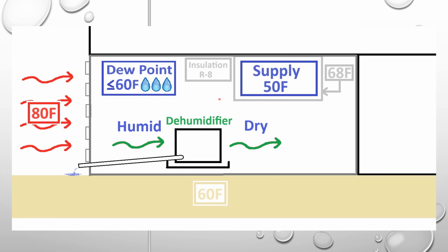If you have a duct system that's in unconditioned spaces, attics, crawl spaces, carports, we can't do anything about the outside temperature. The only time I get the chance to control that temperature or to stop the humidity from going in there is if you put an encapsulation around that, an encapsulated attic or just sealed up boxing. Otherwise, it's equivalent to putting a water pump in a lake, putting the hose back in the same lake and expecting that lake to pump out. The better sealed the area, as long as you don't have cracks and holes in that encapsulated area, the less the dehumidifier will run, which will be more efficient.